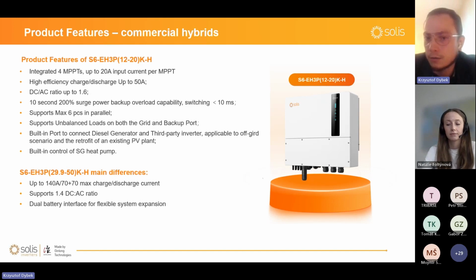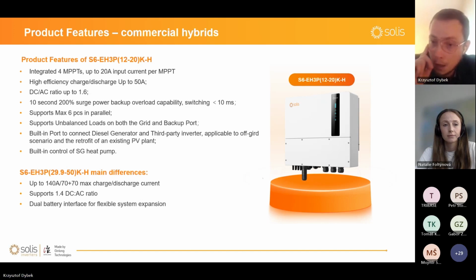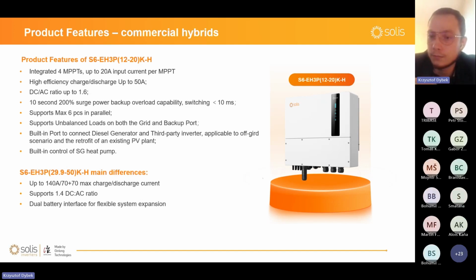So 10 seconds, 200% surge power backup overload capability. Switching is less than 10 milliseconds. About paralleling, I told you. For parallel can be one master and the rest are slaves, as the communication is through RS485 and Modbus RTU. If you need some export limitation on site, you can use EPM device connected as well if you use also grid-tied inverters.